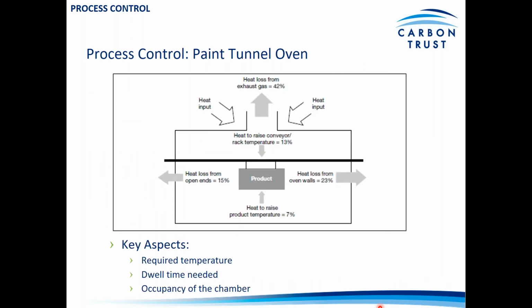And controls come into play even more so in high intensity systems. The example we have here is for a paint tunnel oven. You can see here that the level of loss is very high, so there are losses from the open ends as equipment comes through the paint tunnel. There are losses through the walls of the oven. There are losses from the exhaust gases, and also the likes of the conveyor and the rack are being heated as well as the product itself. So in this example, we're indicating that the heat required just to heat that product and to cure the paint is just 7%. So given that intensity, controls are very important.